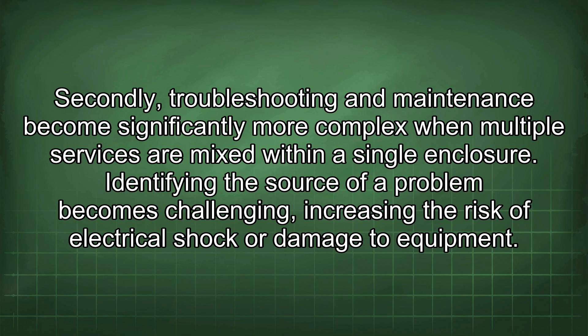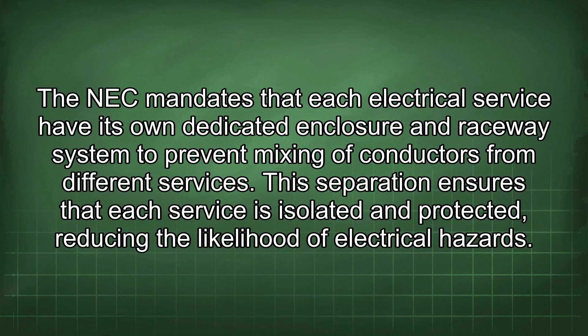The NEC mandates that each electrical service have its own dedicated enclosure and raceway system to prevent mixing of conductors from different services. This separation ensures that each service is isolated and protected, reducing the likelihood of electrical hazards. Article 230 of the NEC covers service entrances and provides detailed requirements for service conductors, including their separation and protection. It outlines the methods for installing service conductors, the types of enclosures permitted, and the clearances required between service conductors and other objects. Failure to comply with NEC requirements can result in penalties, including fines and potential legal liabilities.